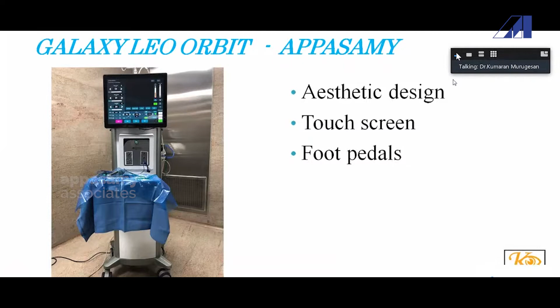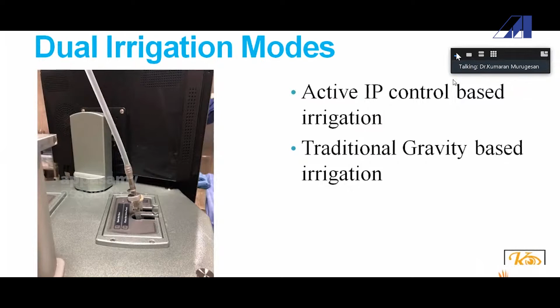machine which has incorporated the active fluidics, or the real-time fluidic system. The highlight of this machine is the real-time fluidics, which has a controlled infusion into the anterior chamber based on the pressure changes inside. Additionally, it also has a traditional gravity-based irrigation system, which some surgeons who are already used to it can use. The custom IP settings or the real-time fluidics can be set somewhere from 50 to 100 based on your phacoemulsifying techniques and the type of cataract.